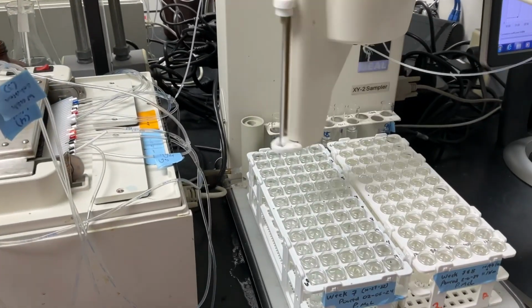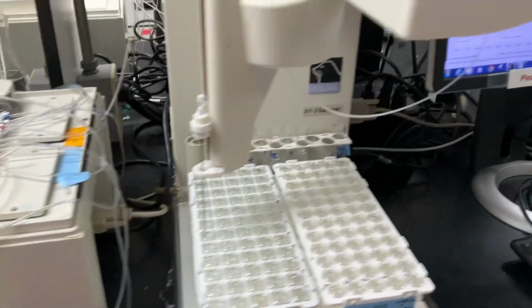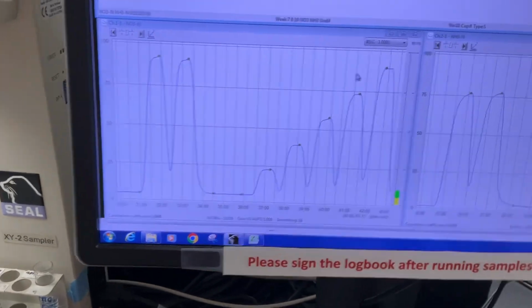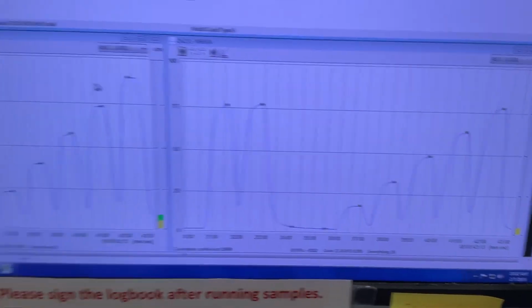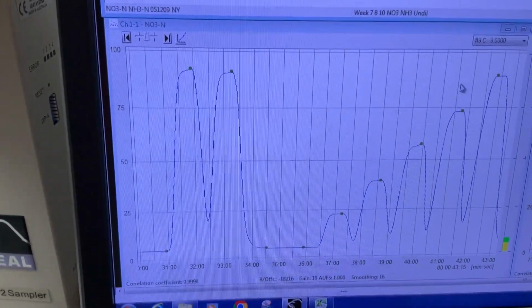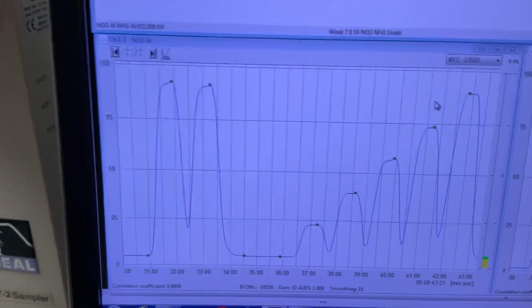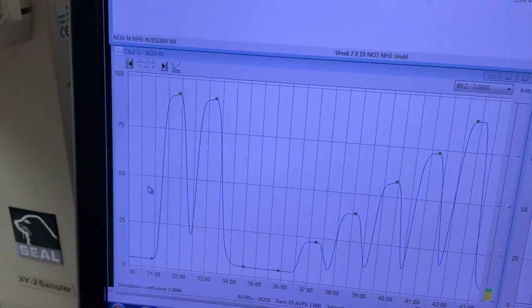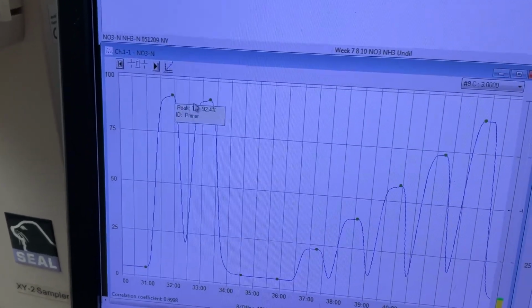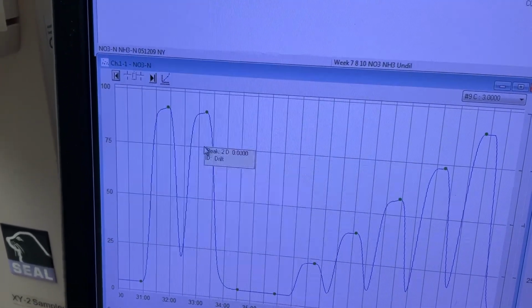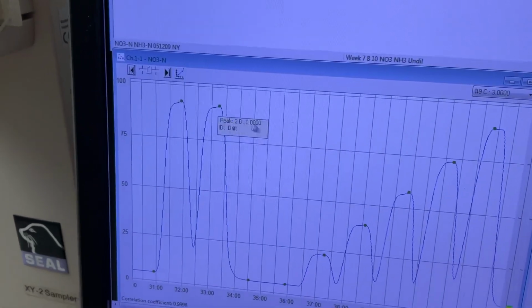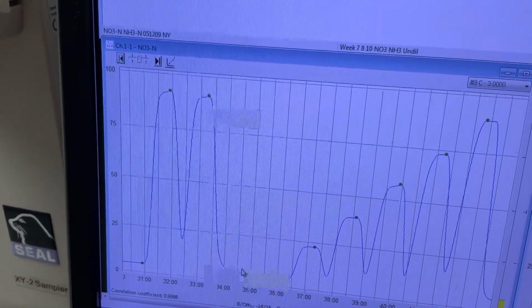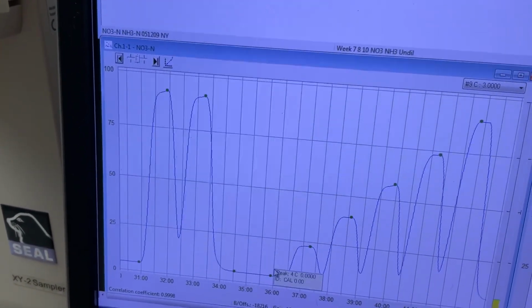Right here we have the machine fully set up. It's running. The probe arm is starting to move to the samples, and you can see on this screen right here this kind of escalating linear pattern. And what that is are the actual standards that have been pumped through the machine at a low level and a high level. And this standard curve that develops is relatively linear, and it kind of just tells you how correlated the machine is to that curve with the known standard concentrations.